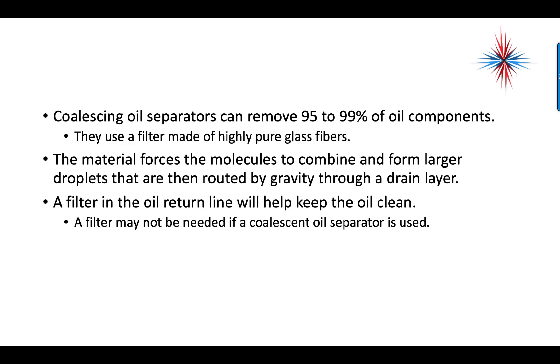Coalescing oil separators can remove 95 to 99% of the oil components. They usually use a filter made of highly pure glass fibers. The material forces the molecules to combine and form larger droplets that are routed by gravity through a drain layer. A filter in the oil return line will keep the oil clean, though a filter may not be needed if a coalescing oil separator is used, as it already filters via the glass fibers.